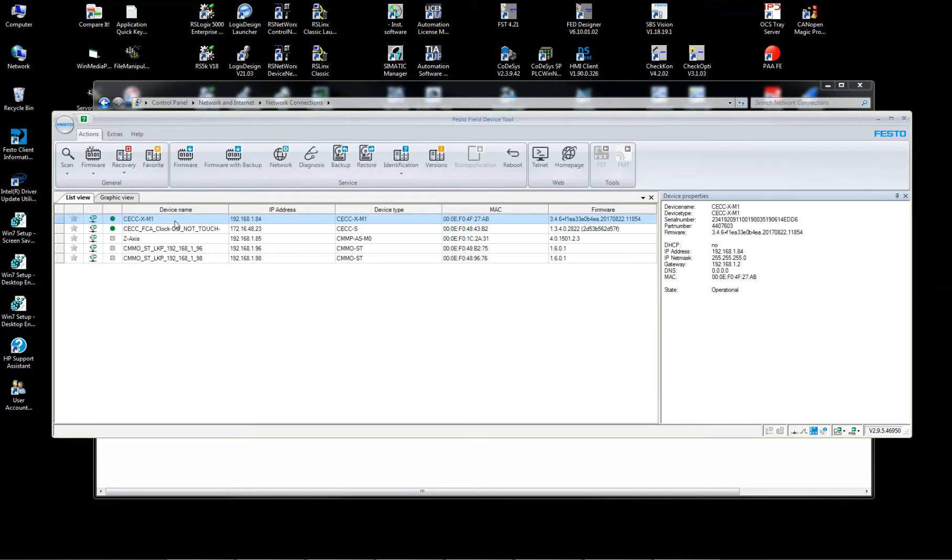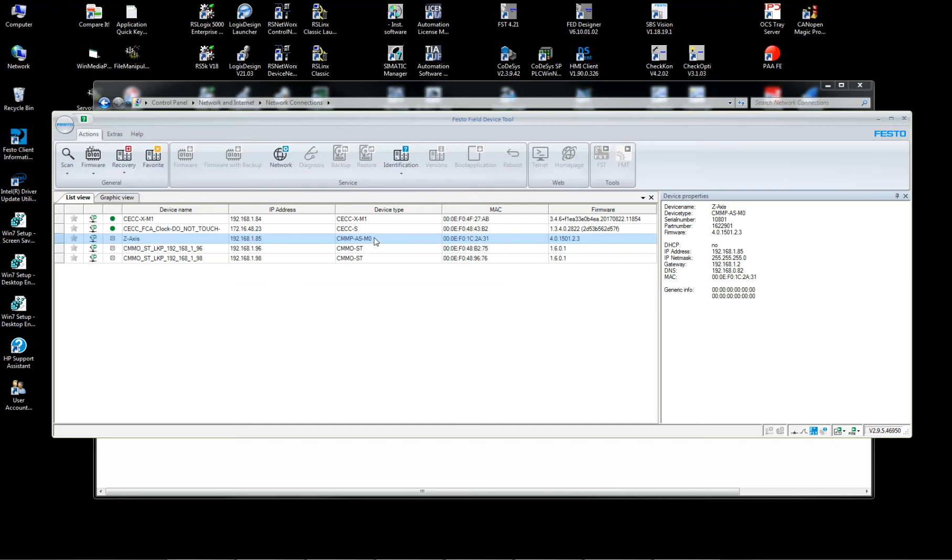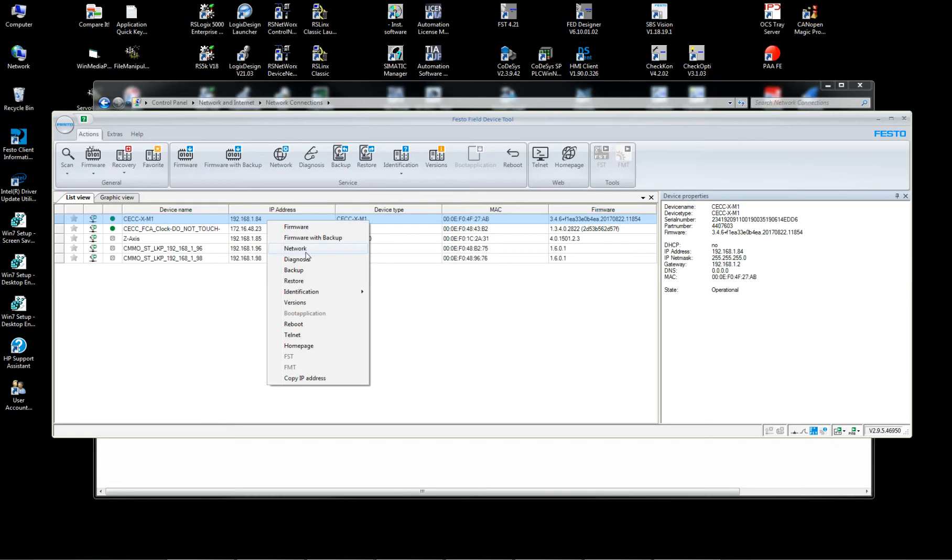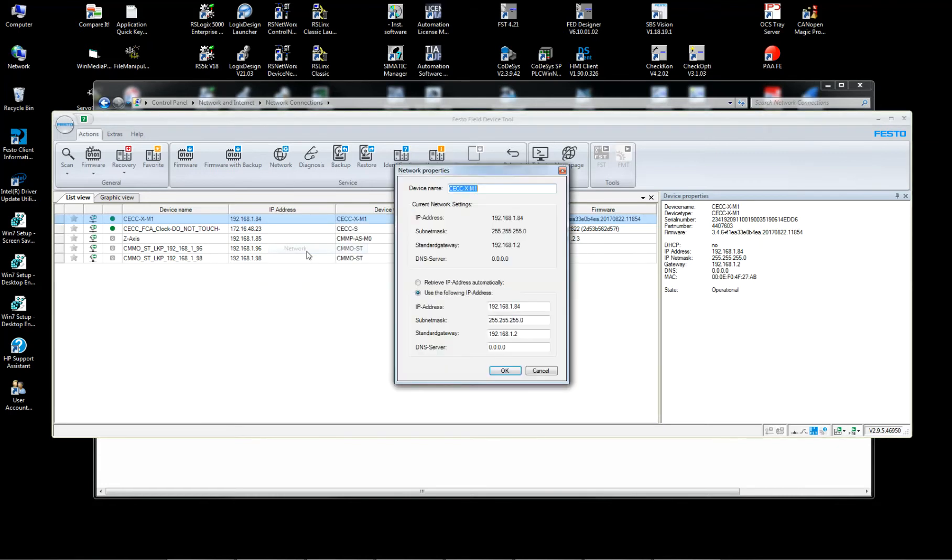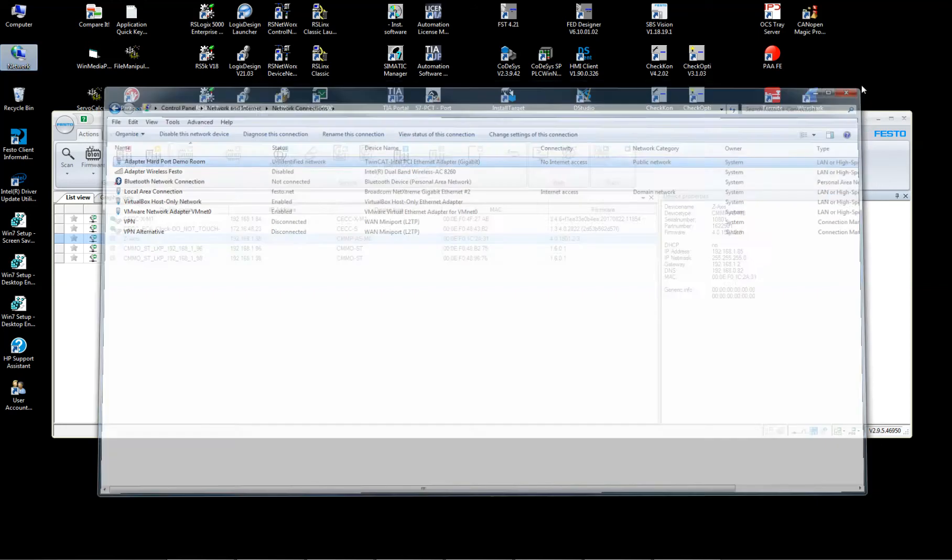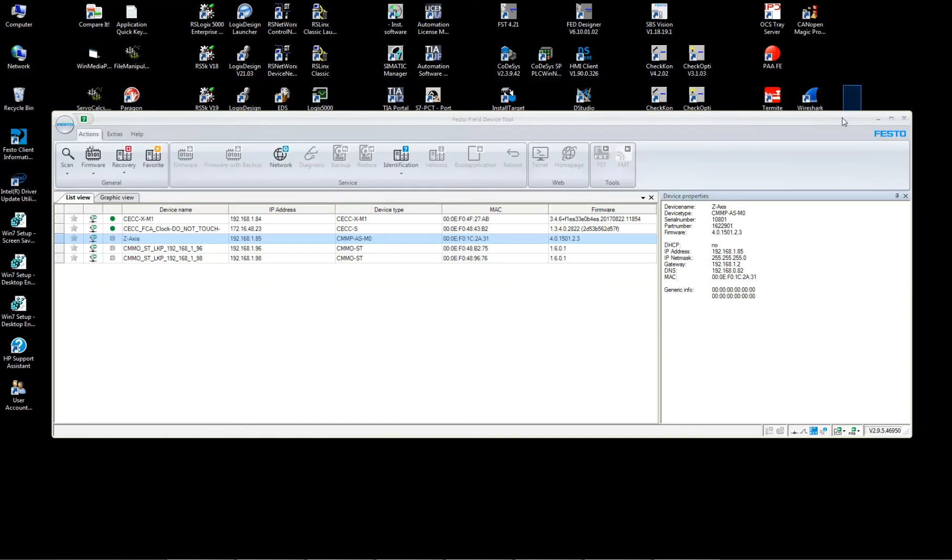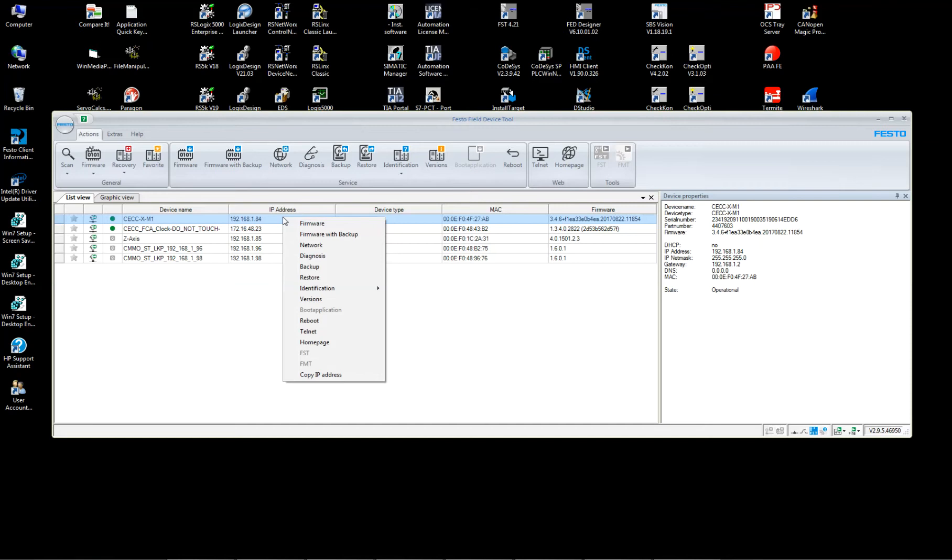And you should see the CECC-X-M1 controller, which is the PLC that runs the servo press. And then you should see the CMMP-AS-M0, which is the servo axis controller. When you select this and you right-click, you go to Network Settings. You can set up your Network Settings right here. And then just hit OK and Apply. The devices both need to be on the first three octets together and then a unique IP, obviously. I've already gone and updated mine to 1.84 and 1.85.